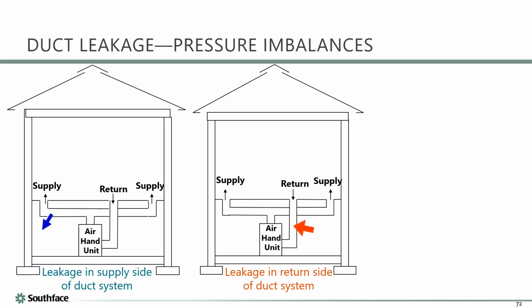I'm going to wrap us up here with talking about duct testing. And I'm going to explain this one by saying, here's a house that I'm just going to use a 2.5 ton air handler on here. So that's about 1,000 CFM. If you have supply leaks, you pull 1,000 CFM from the house, you throw away, let's say 100. That means only 900 goes back in. The house is getting 900, but you're taking out 1,000. So your house pressure goes negative.